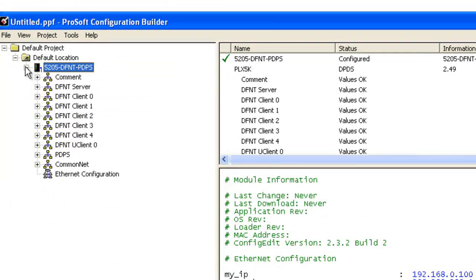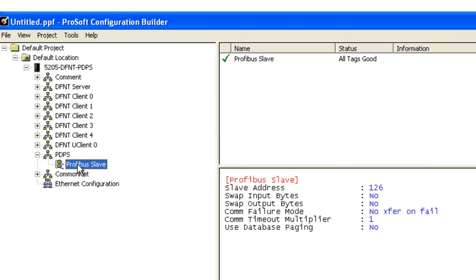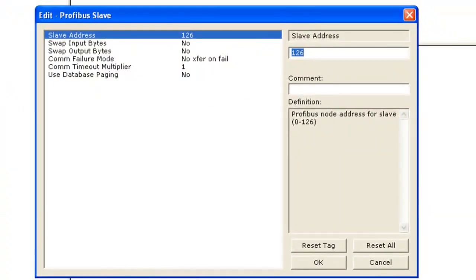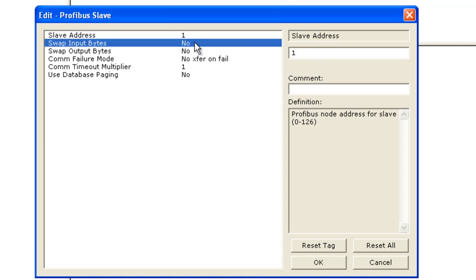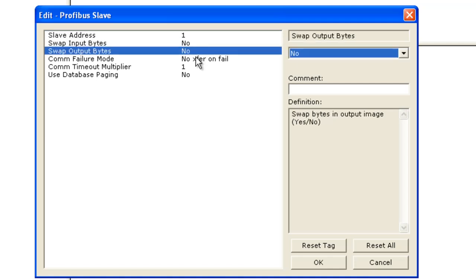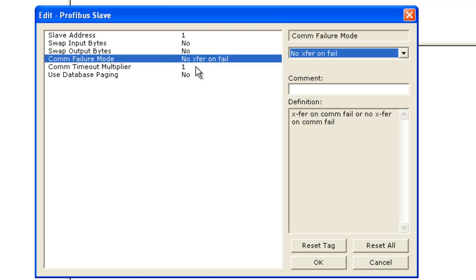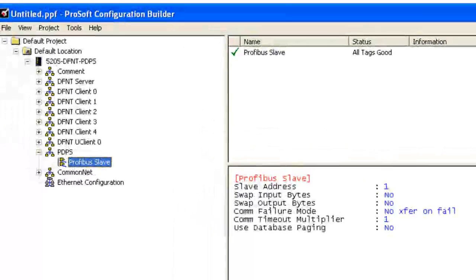Now we expand this and that will show us the PDPS. Expand that and right click here and now we can go ahead and configure the Profibus Slave. There's only a couple options. The first one is the Slave Address which we're going to be Slave 1. Swap Input Bytes and Swap Output Bytes. That's going to be swapping data. Stop Transfer on Communications Fail and a Comm Time Out. And we'll just click OK.